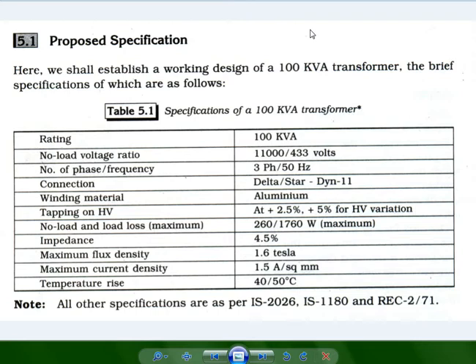If your transformer tank does not cool down, eventually this means the winding may be working at 80 or 90, and the tank working at 70-80 or above. So what will happen? There will be degradation of the resistance, degradation of the oil, and all other factors coming in.